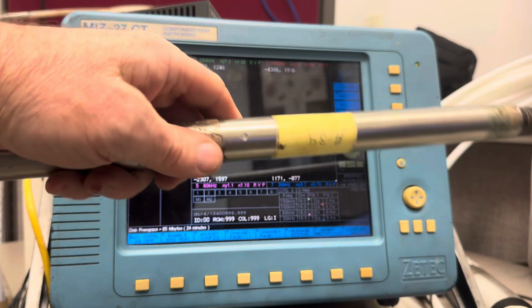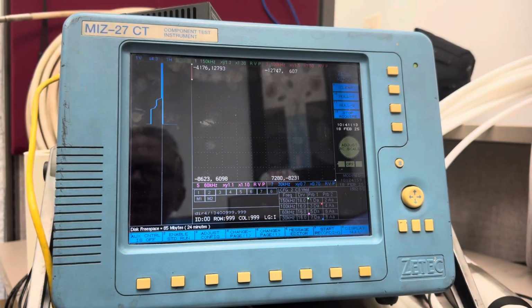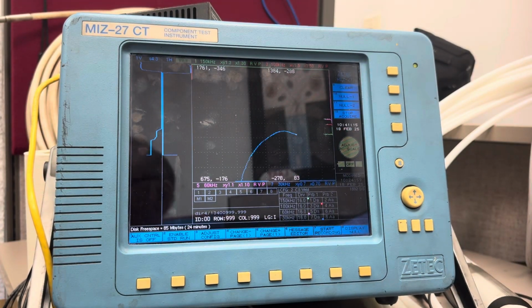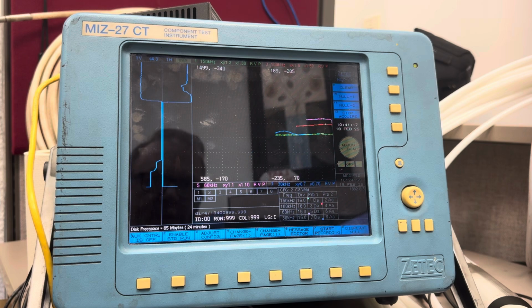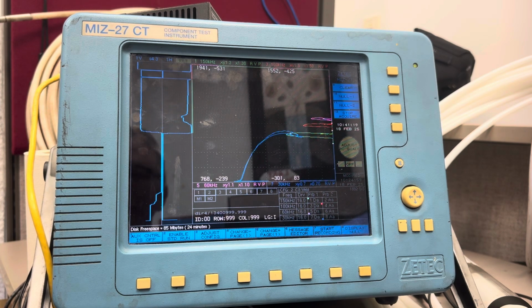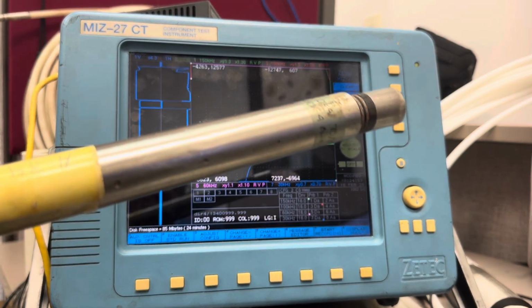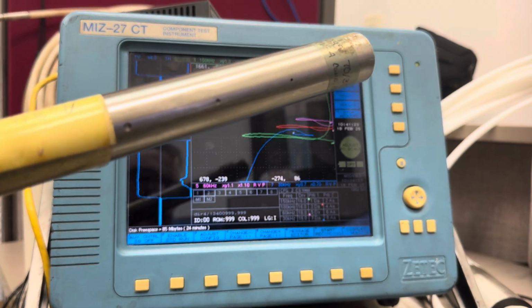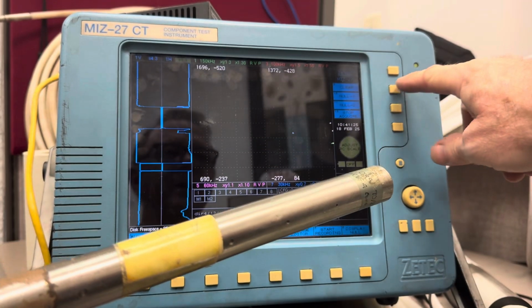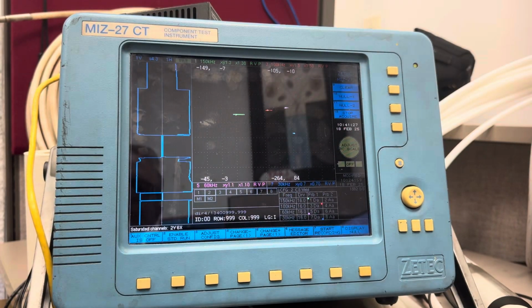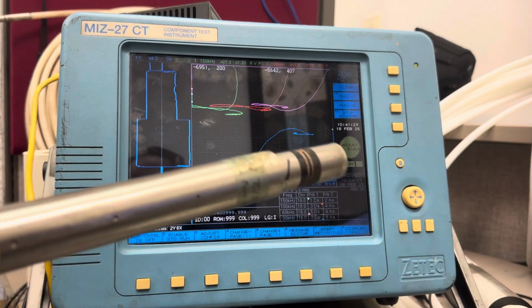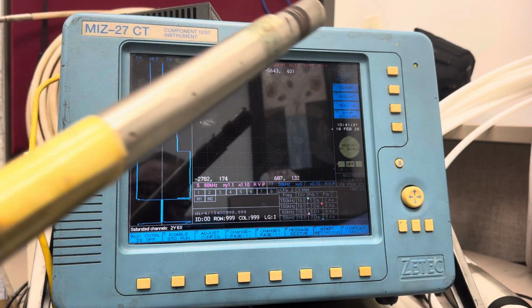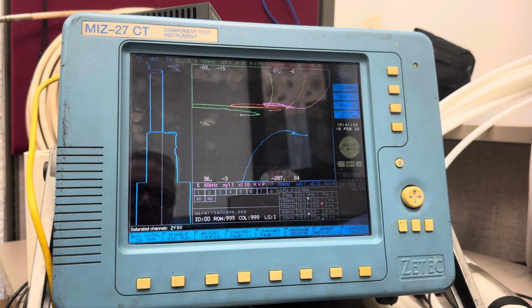And you can see here's the bobbin calibration standard. It's 1 inch by 0.049. This is 7030 copper nickel. So I have my probe just inside of the standard. I'm going to hit null. I'm going to push the probe out, and then I'm going to slowly pull it back.